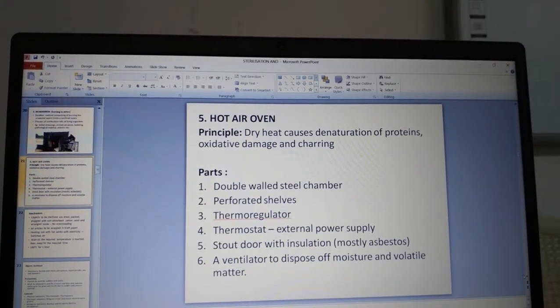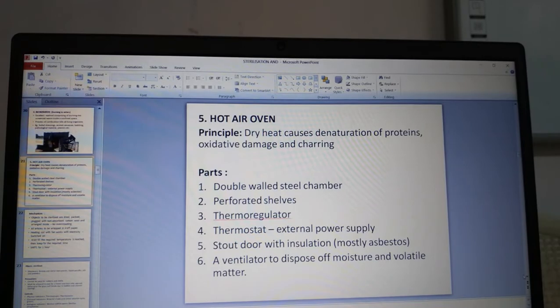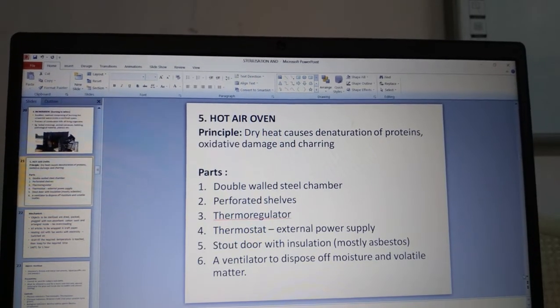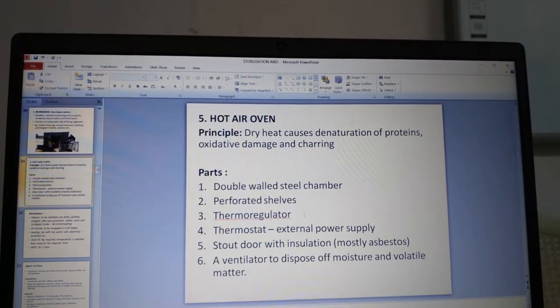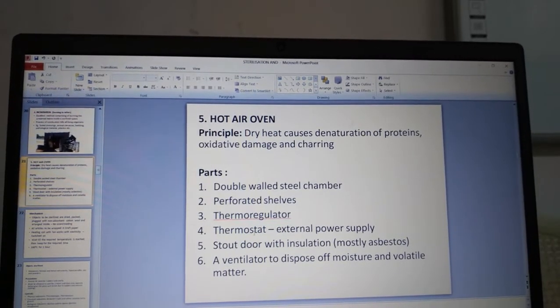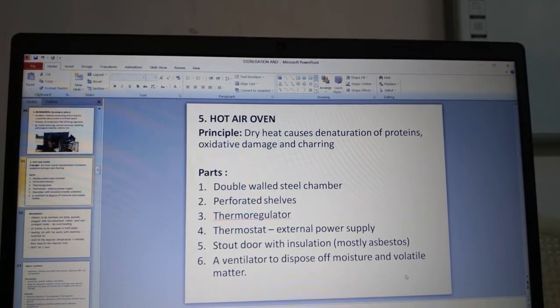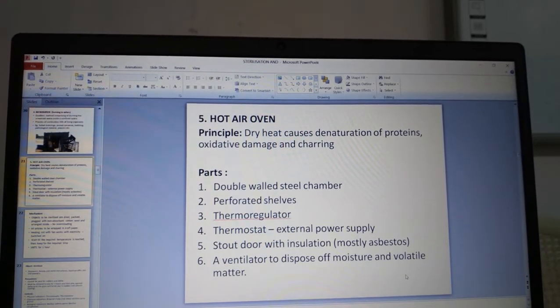The hot air oven works on the principle of dry heat, causing denaturation of proteins, oxidative damage and charring. Its parts include a double-walled steel chamber with perforated shelves, a thermoregulator, a thermostat with external power supply, a stout door with insulation (mostly asbestos), and a ventilator to dispose of moisture and volatile matter.